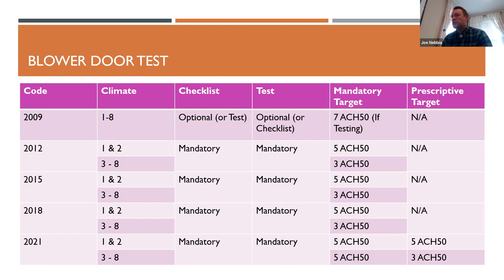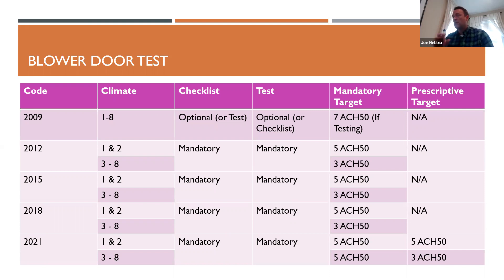2015 and 2018 kept the same requirements: the mandatory detailed checklist and the mandatory blower door test, with those targets remaining mandatory. So if you were in Chicago and missed the 3 ACH-50, that was enough to fail you according to the IECC. It was a very challenging test because if you miss the target, the house doesn't pass, you don't get your certificate of occupancy, and you have to go back and air seal a whole bunch of things and retest. You can't say, well, I've got more efficiency somewhere else. If you fail, it's going to be a costly mistake.